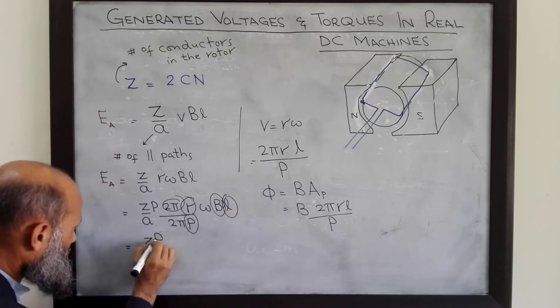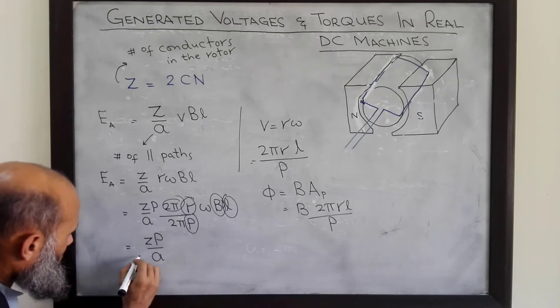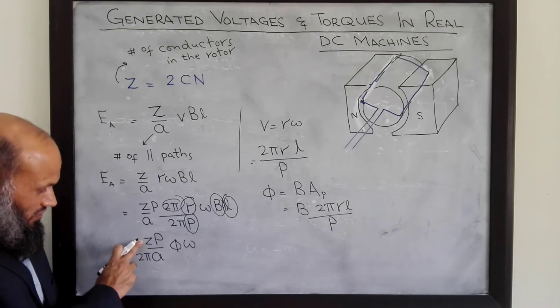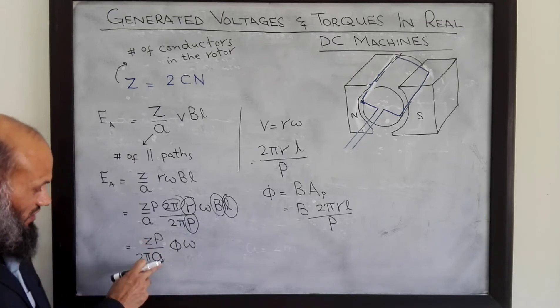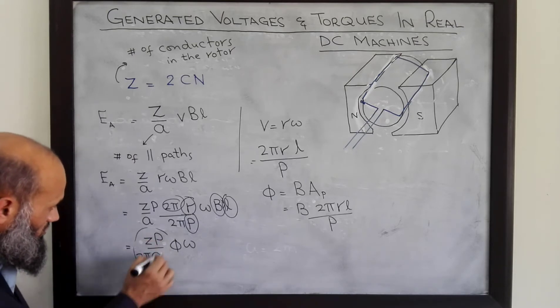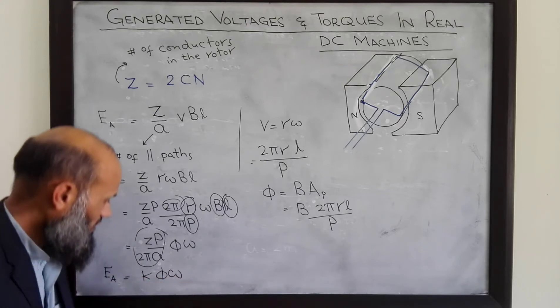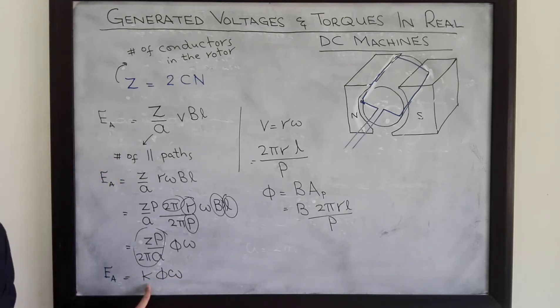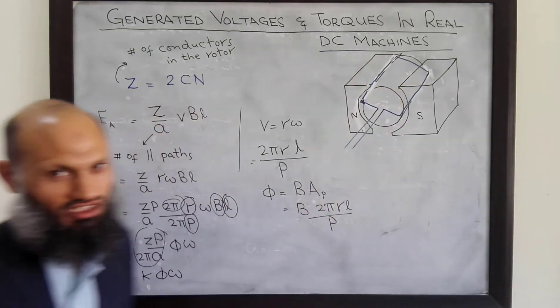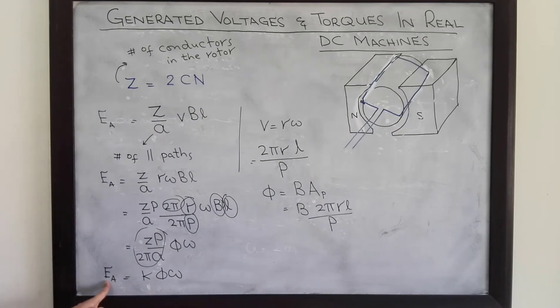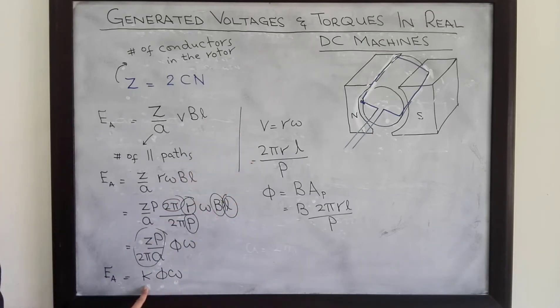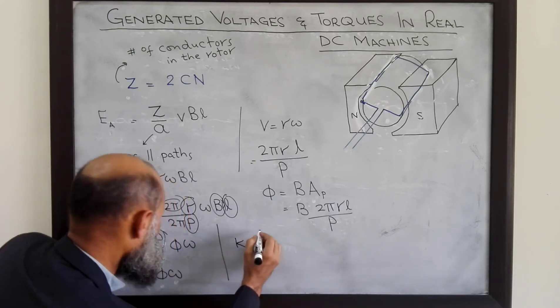This gives EA = (ZP)/(2πA) × φ × ω. Once the machine is designed, the number of conductors Z, number of poles P, and number of parallel paths A are all fixed. Therefore EA = K·φ·ω, where the constant K = ZP/(2πA) depends on the construction of the machine. This expression is quite similar to the one derived for a single turn — the generated voltage depends upon the total flux, the speed of rotation, and a constant.